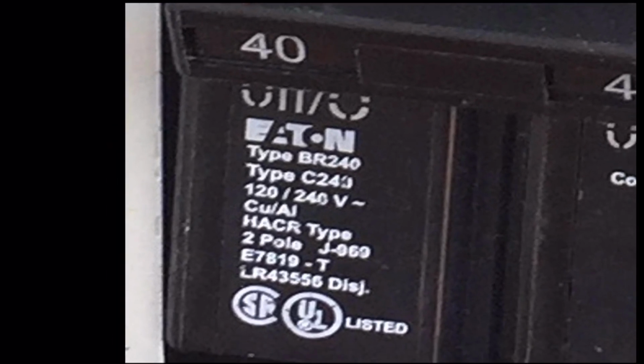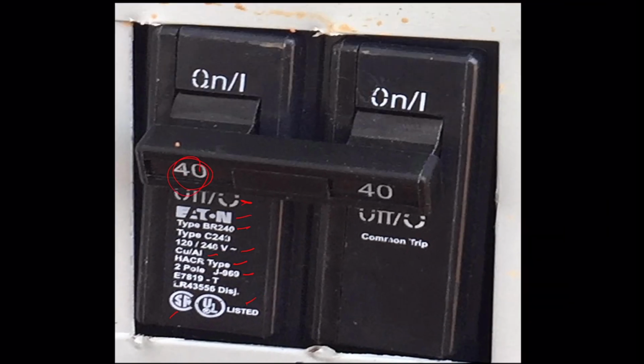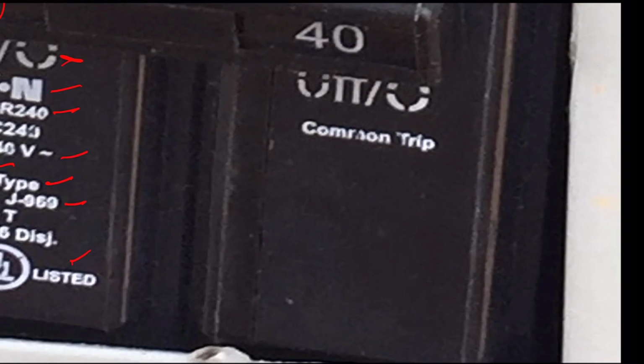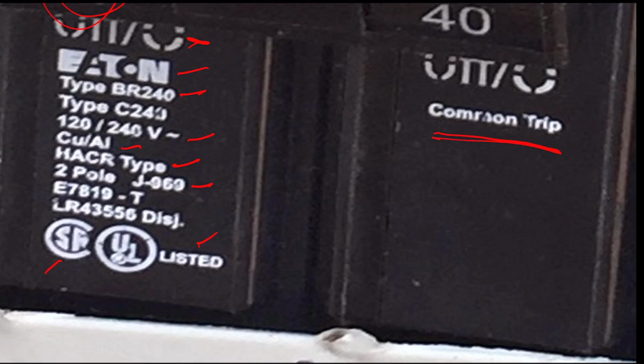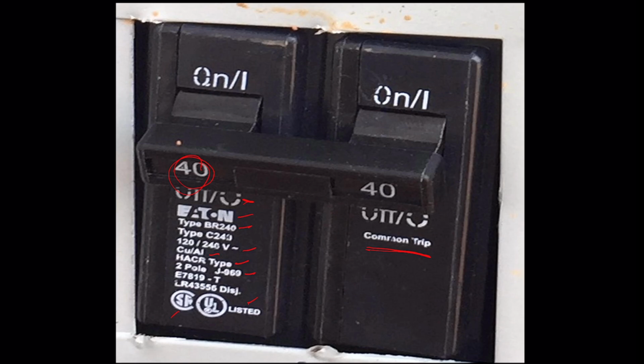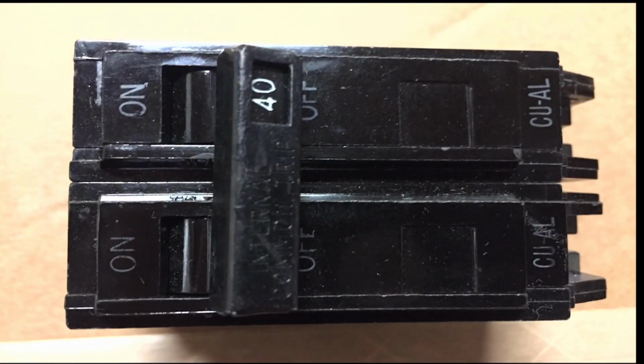So there's a lot of information on the front of that one. Here is the front of this one. So you have the type, you have the manufacturer, you have the voltage, copper or aluminum, HACR, how many poles. You've got the UL and CSA listing marks. You've got on-off, and you've got the current rating. There's a lot of really good information there. All right. Oh, and look at that, common trip.